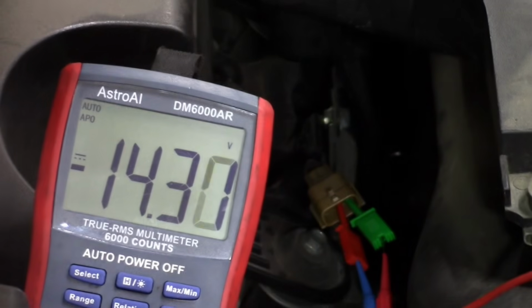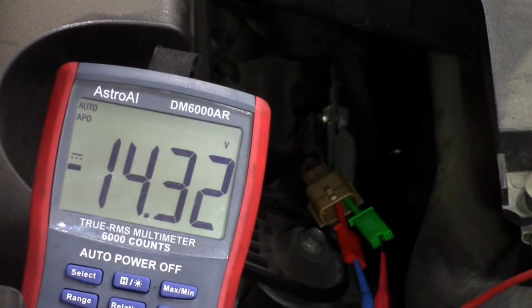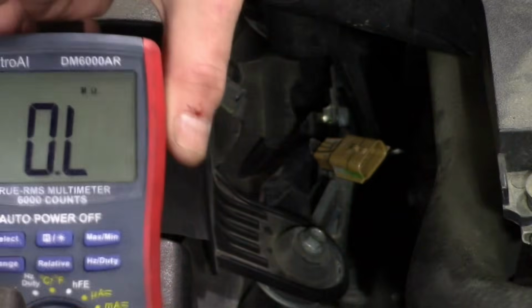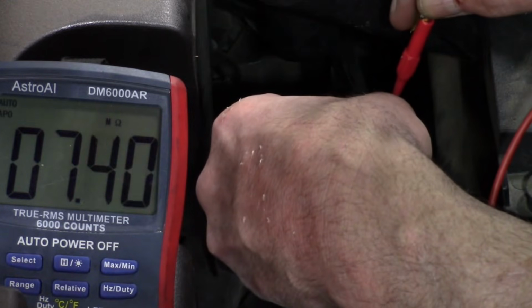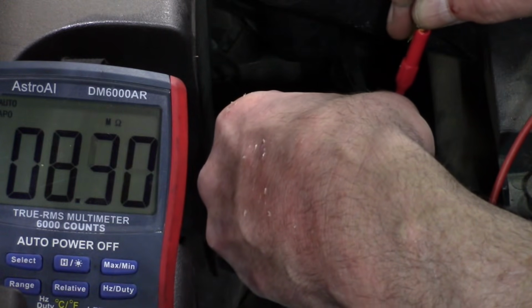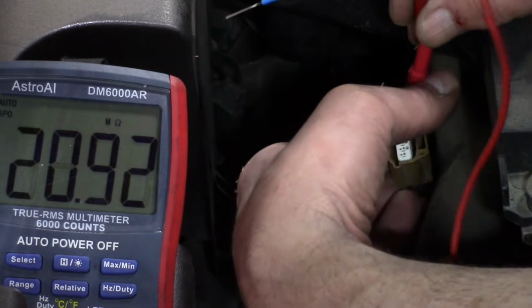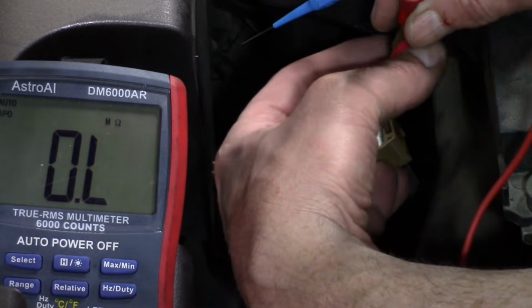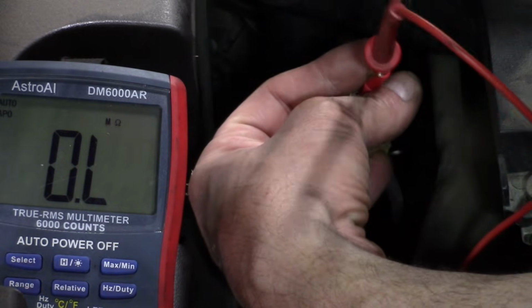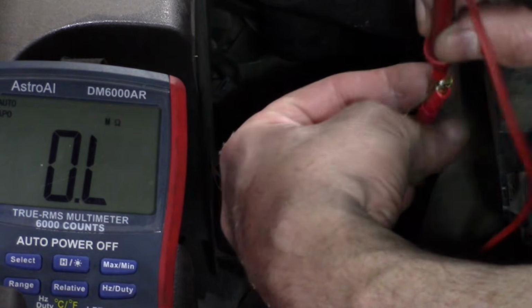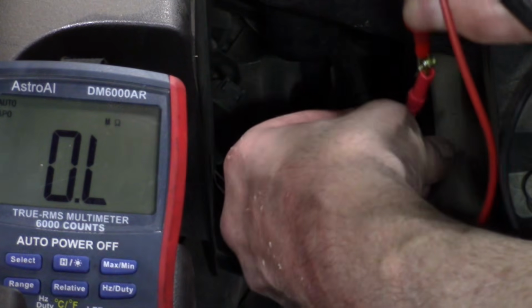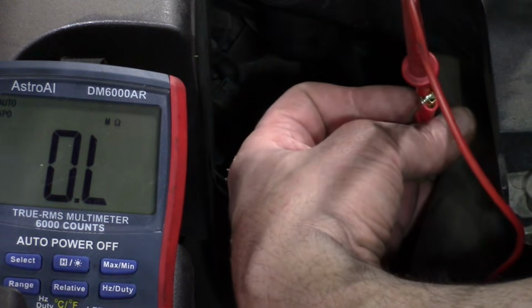We've got an issue with the sensor itself, so let's check there. Now going to turn my meter over to a continuity measurement. Testing our same colored wires here, we want to just barely touch these terminals. We don't want to spread them apart and cause a connection issue. I expect we should see usually about 3.5 ohms or so.